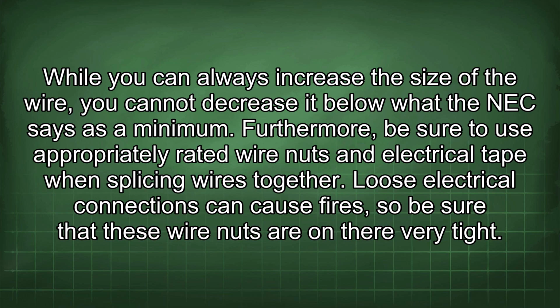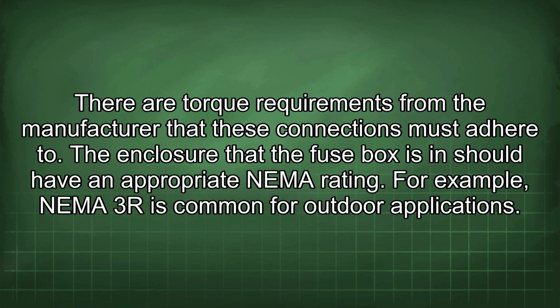Furthermore, be sure to use appropriately rated wire nuts and electrical tape when splicing wires together. Loose electrical connections can cause fires, so be sure that these wire nuts are on there very tight. There are torque requirements from the manufacturer that these connections must adhere to.